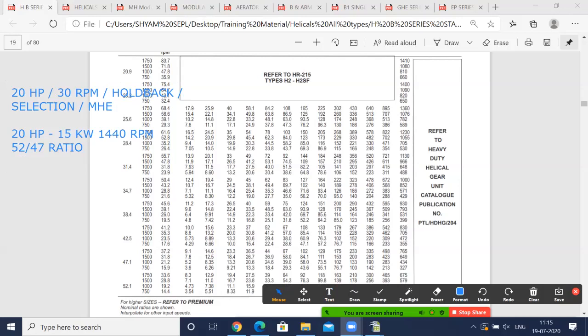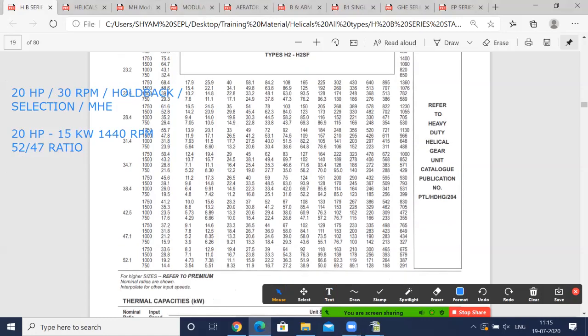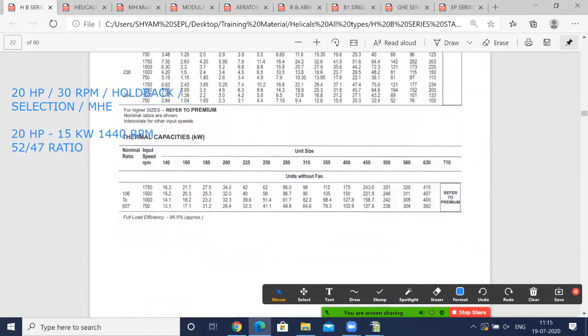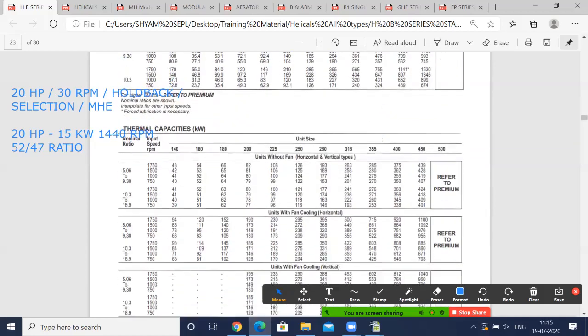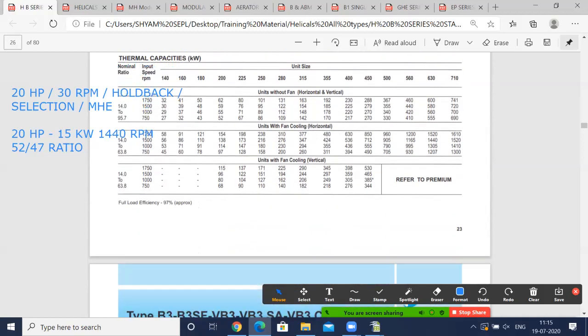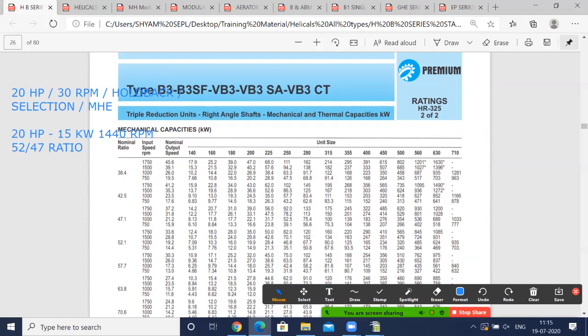Okay, so 15 kilowatt, 30 RPM, so we'll need around a 50 ratio. H3, no, we are going for bevel. So let's go to B2. B2, no, 50 ratio, not there. 50 ratio, you can stop. Yeah, 47 ratio and 52 ratio. You can see 32 RPM here and you can see 29 RPM here. So both are acceptable. So here the kilowatt rating, 15 kilowatts, you'll be searching for something like 25 to 30 kilowatt in this case, with a normal heavy duty.